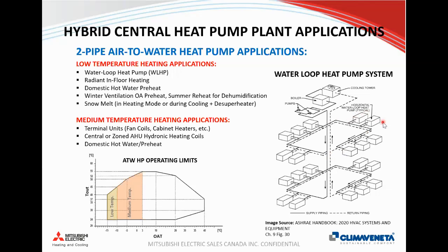So typically the best way to do this system would be geothermal. But when geothermal is not feasible or it's too expensive, typically these systems will go cooling tower boiler. So we have a cooling tower to reject heat from the loop on the warmer days in summer. And on the colder days in winter, we have a boiler to inject heat into the system. During about +10 to +20 in the shoulder season, we don't necessarily need to add heat or reject heat from the system, because you could have some units that are in heating and others are in cooling. So you're actually going to exchange heat through the water loop, depending on the piping configuration, of course.